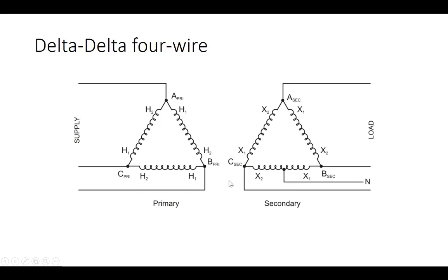And that's really all you need to know for delta to delta 4 wire three-phase transformers. The only other thing to keep in mind is that code is very clear about the fact that on the secondary of this transformer, when we feed panels with this secondary, the only thing that we can have in a single phase panel is line B, line C, and this center tap neutral. We cannot have line A in a single phase panel because that will not give us 120 volts. It will give us a higher voltage, 208 volts, and so we cannot have line A in a single phase panel.